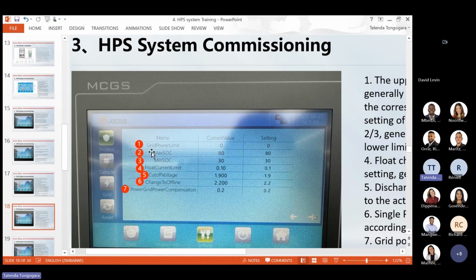Okay, now we have grid power. Sorry, I think I skipped something. Okay. We have grid power limit. This is the limit that you want your inverter or your HPS to take from grid. So you can set it to 50 kilowatt, you can set it to 100 kilowatt, depending on how much you can get from your transformer, the client side transformer. So if you cannot get more than 100 kilowatt, but you have an HPS 150, you just set it to 100 kilowatt.